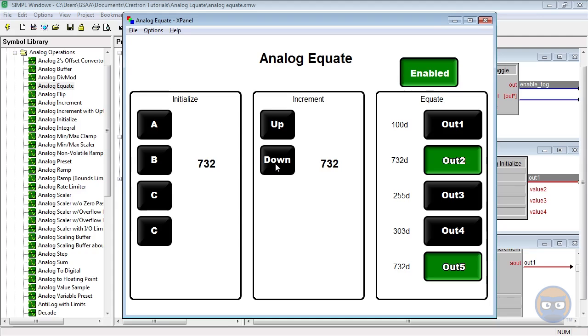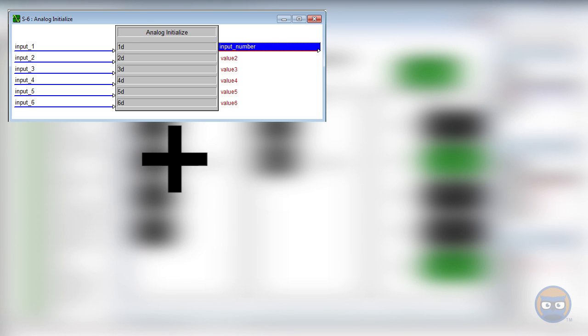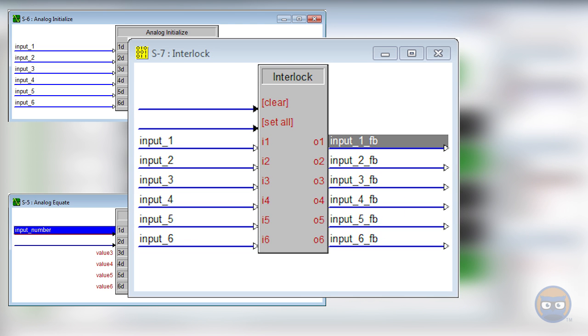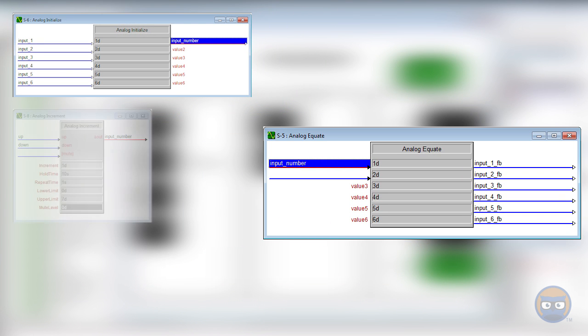So when is it good to use an analog equate? In our experience, the equate usually goes hand in hand with an analog initialize. If the parameters of both symbols are matched up with the same values, they start to behave like an interlock. The only difference is that you don't have a set all option. The advantage of using this over a regular interlock is the ability to jam analog signals. Your selection can be modified from the output of any analog symbol, without dealing with the fuss of having to redo a ton of digital logic.